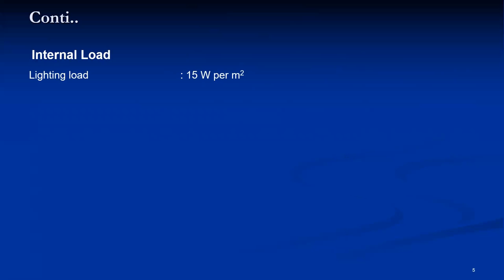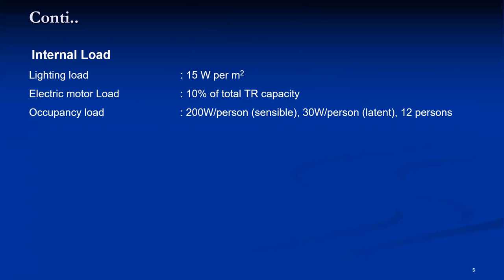The internal load data includes lighting load of 15 Watt per meter square, taken from the design data book for cold storage. The electric motor load is 10% of the total TR. For occupancy load, there are 12 persons working in the cold storage for loading and unloading, each dissipating 200 Watt sensible heat and 30 Watt latent heat. The air changes per hour — which is actually the leakage rate — is 0.25, which is always less than 1 for cold storage, as recommended. For normal air conditioning rooms, this value is 5 to 10, but for cold storage the high value is not recommended.